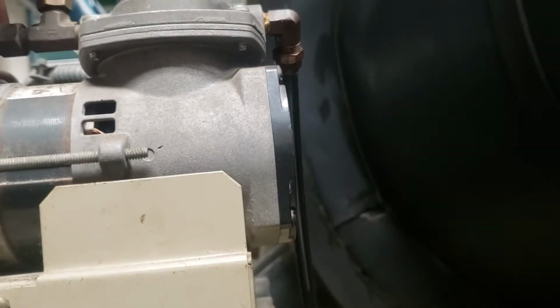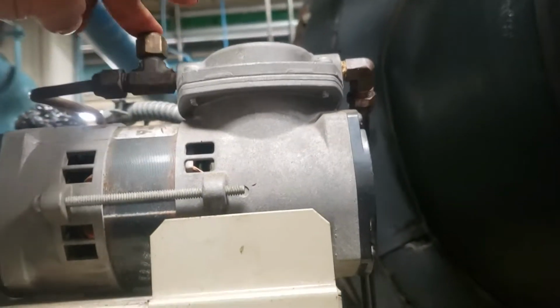So far, I don't see anything wrong with the purge unit. I know my solenoids are opening up, because when the pump-out machine is running, you can take this off and you can feel air coming out and the suction in here. So you know that's working.